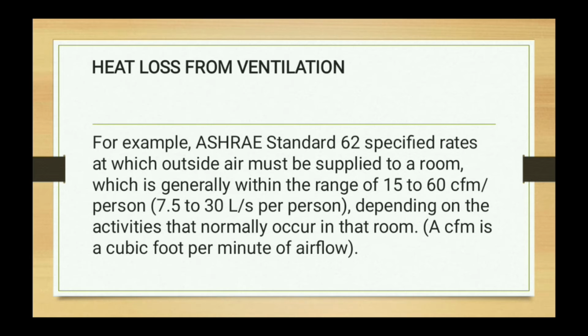For example, ASHRAE standard 62 specified rates at which outside air must be supplied to a room, which is generally within the range of 15 to 60 cubic feet per minute per person, depending on the activities that normally occur in that room. So, i-assume natin na yung classroom daw ay may space na nakadesign for an occupancy of 30. Then, the ASHRAE standard calls for a minimum outside airflow rate for the classroom of 15 cubic feet per minute per person. So, therefore, yung classroom daw, kailangan niya ng 15 cubic feet per minute per person times 30, or 450 cubic feet per minute.